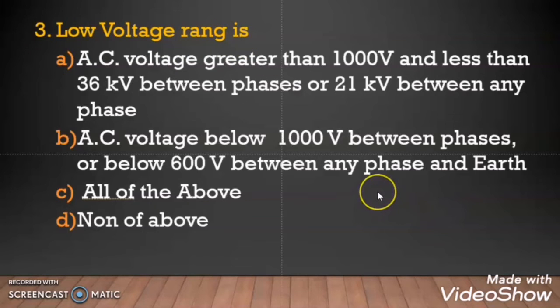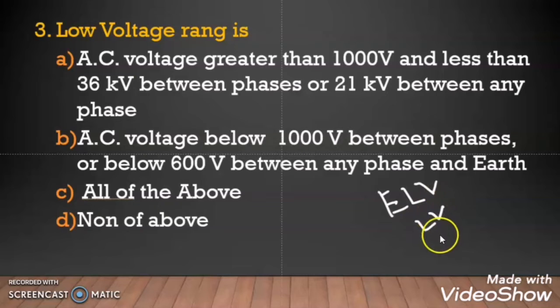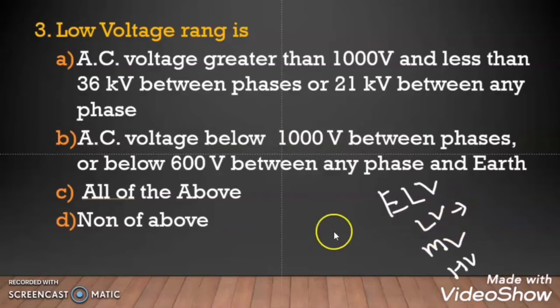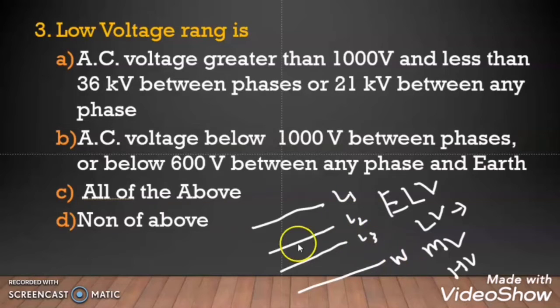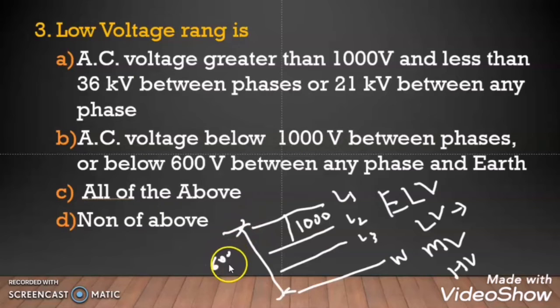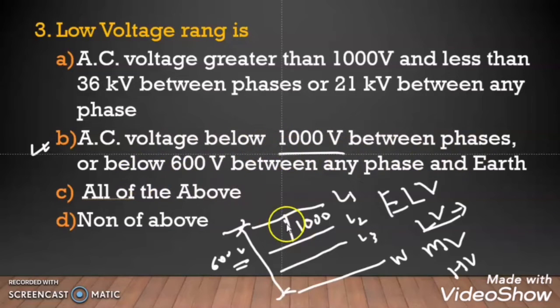Question 3: Low voltage ranges. There are different voltage levels — ELV extra low voltage, LV, medium voltage, and high voltage systems. In a 3-phase system with Line 1, Line 2, Line 3, and neutral — when the voltage between any line to other line is 1000 volt or less, or the voltage between line to neutral is 600 volt or less, that system is called a low voltage system. So option B is correct: AC voltage below 1000 volt between the phases, and below 600 volt between the phase and earth or neutral.